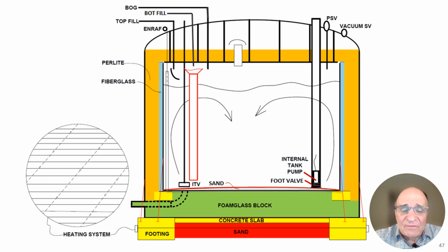And what about that frost heave that I was talking about? Well, you want to prevent this underground from freezing. And in order to do that, if you're attached to the ground, if you're in touch with the ground, you want to have heating cables in there. And these are your heating cables. And the way the heating cables are put, like this, conduit, conduit, conduit, conduit, conduit, and you're running typically 3 number 12 wires through this conduit, and you're running voltage or power supply to those electric wires. Typically, it's 3-phase 480 volt. And I'm saying typically only from my experience of the facilities that I've been at. It doesn't have to be that voltage.